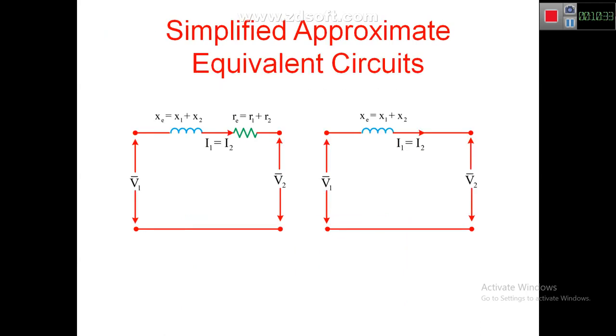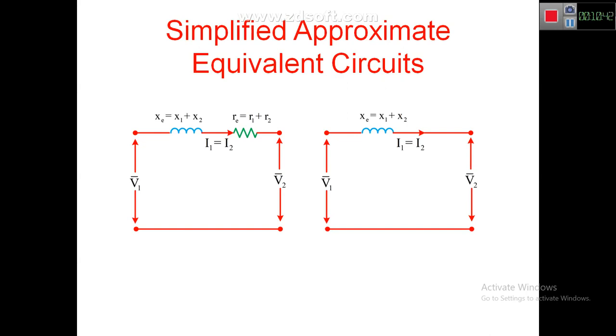For approximate equivalent circuits, resistance and inductance are simply transferred to one side — either primary or secondary. The first form is referred to secondary side and the second to primary side. These are called approximate equivalent circuits, keeping the shunt branch as is. All resistances and inductances are moved to the left or right side to form the approximate equivalent circuit. In the simplified approximate equivalent circuit, the shunt branch is neglected, leaving only re and xe.